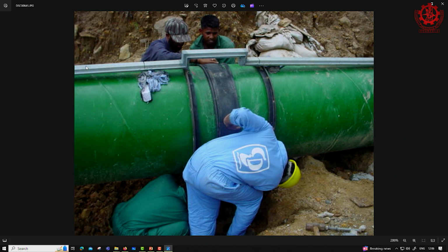Here this is the path for the cable coming from the water level sensor to the water level controller in the powerhouse. We have a power line also to take power to the forebay tank. So, the forebay tank people can have some electricity, right, otherwise they will be in the dark during night time. So, we have power lines as well as this signal cable which is taking the water level sensor signal to the powerhouse water level controller.